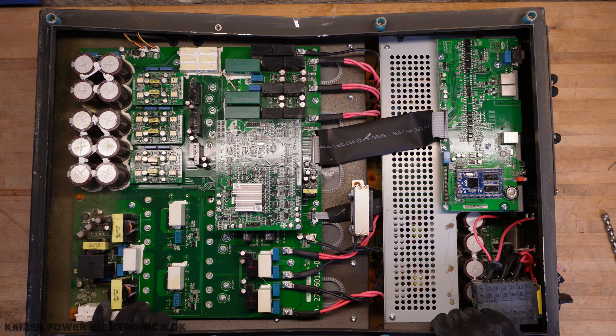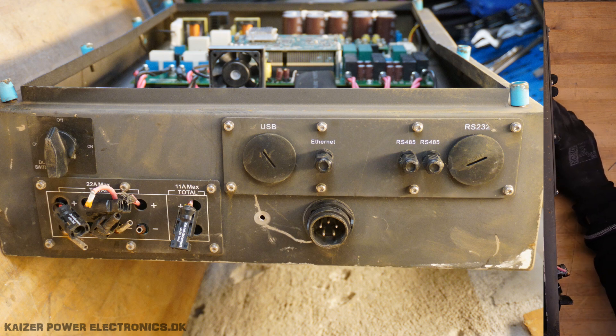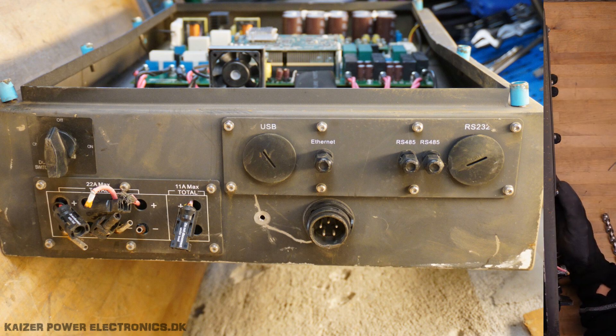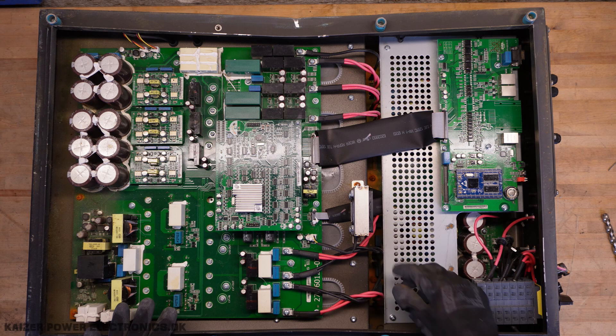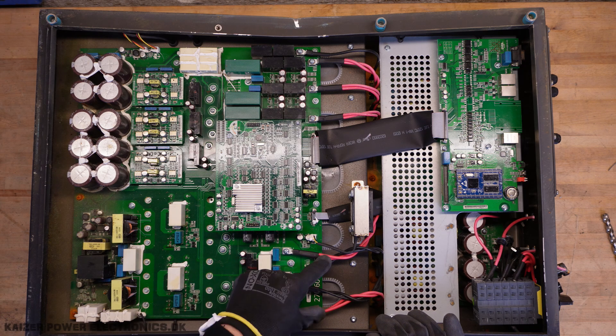This is an extremely heavy solar inverter. Let's go through the inputs and outputs down here — you will have to do with a still picture. First we have the input-output DC switch for the photovoltaic panels, and then we have what seems like 10 connections to strings, so that's a total of 5 different strings. Then there is a USB, Ethernet, RS-485, and RS-232 serial connections, and then we have the mains plug. We now know that we have the PV voltage input over here down the right side, with what seems to be two strings going up here — positive-positive and a common negative, or maybe two separate rows.